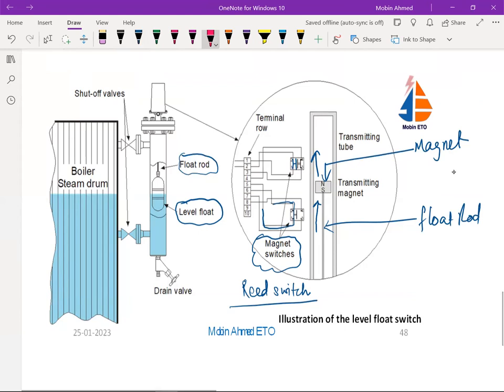Now when it is going to come back from here, like it is going down, in this case again the status is going to change. Okay, this status will change. So this status changes every time when the magnet is passing. Magnet is going up, it will go to this side, and when it is coming down, it will again come back to this side. Here also the reed switch is going to happen. When the magnet is moving up, this will move this side, and when it is going to come down, it will move this side. Okay, so its status is changed, and this is how this magnetic switch is going to work.